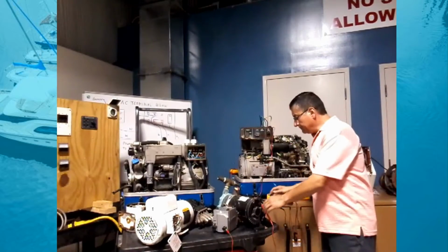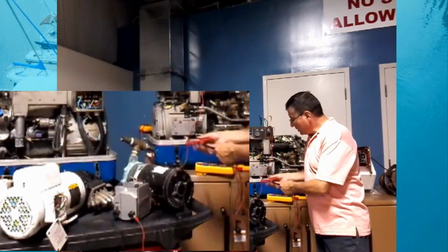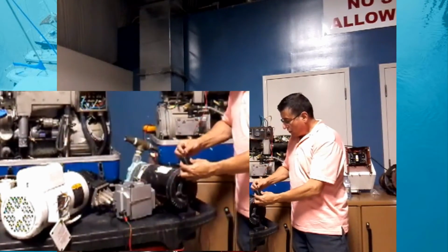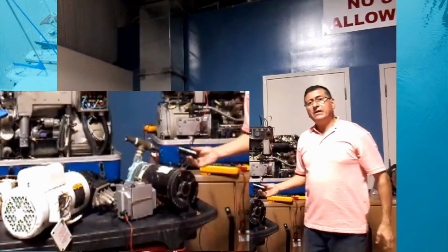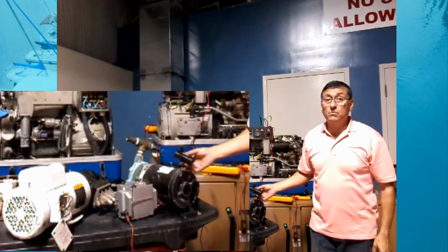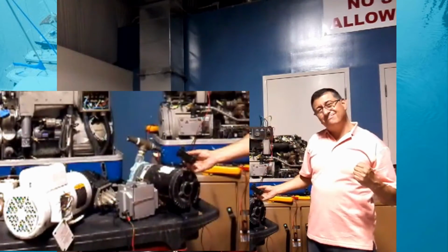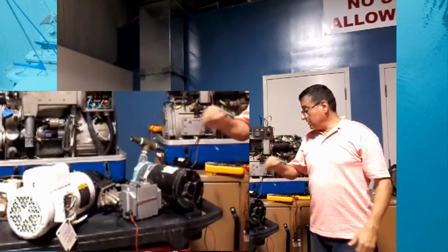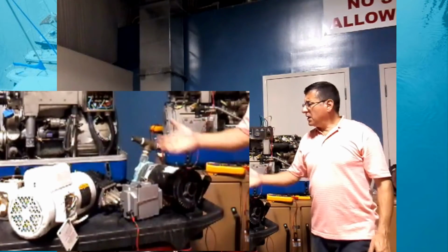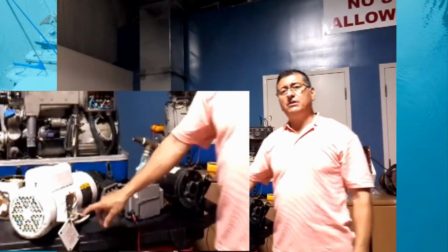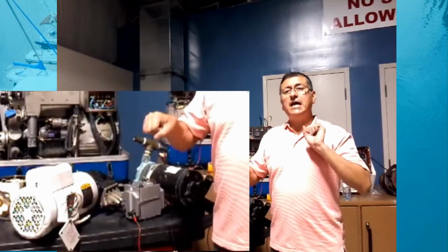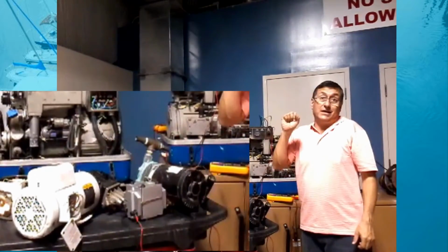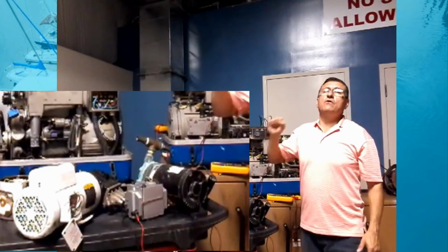Normally, for example, this is a single-phase motor. Remember, the single-phase motor always uses capacitors. The capacitor is used in single-phase induction motors, AC motors, to produce an extra voltage at the beginning in order to produce extra torque. This is used normally in single-phase motors. In three-phase motors, you don't need capacitors. You have the phases at different angles, and the torque produced is excellent in comparison with the single phase. It is only like one piston to move the rotor.